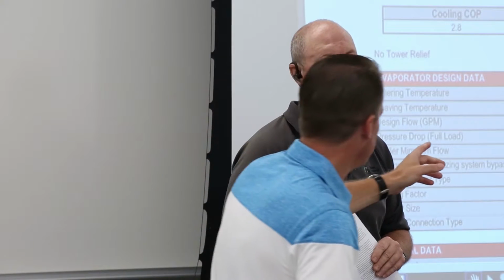It's a heater first whenever you have campus chilled water, and it's a chiller second when you don't have campus chilled water. So you have a minimum flow set up for that condition. Is there a minimum? Yeah, and it's listed right here, chiller minimum flow, is 226 GPM.